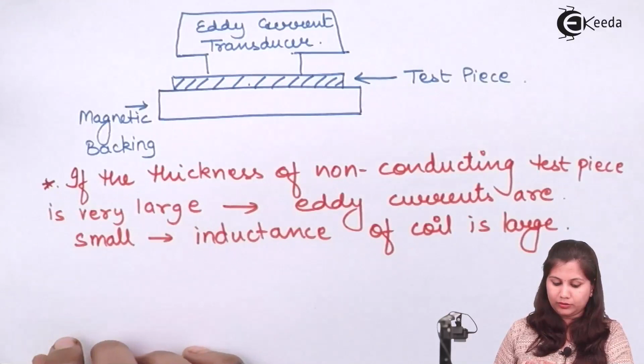Now what will be the arrangement for non-magnetic and non-conducting materials? For that, the test piece is located over a magnetic backing. This is the magnetic backing, this is the test piece, and over it we have the eddy current transducer.